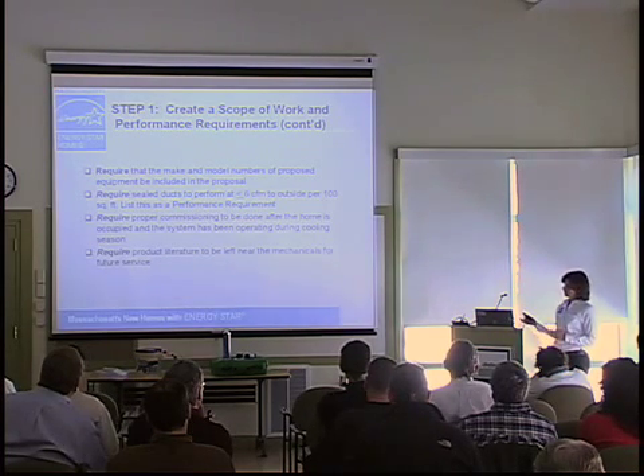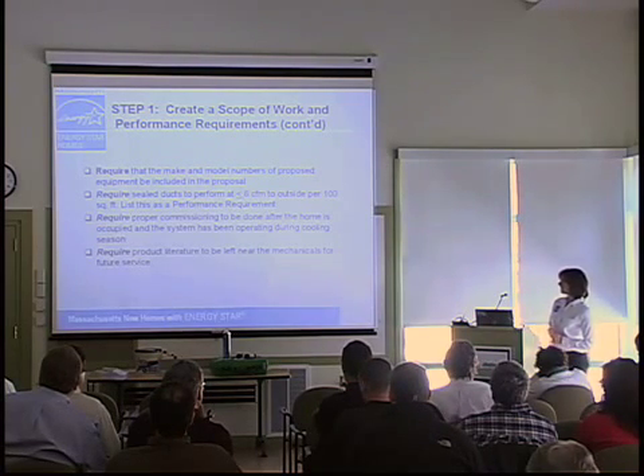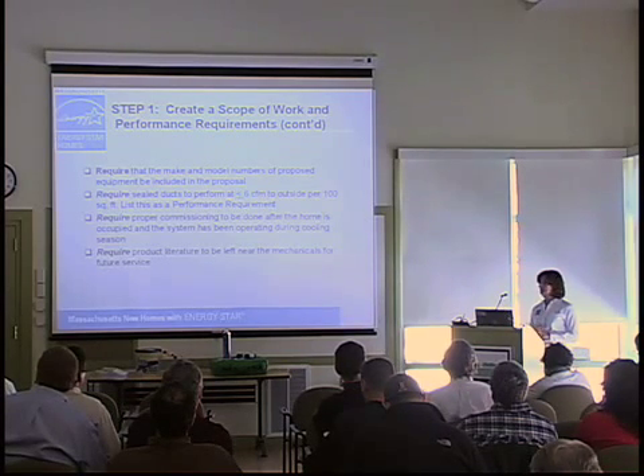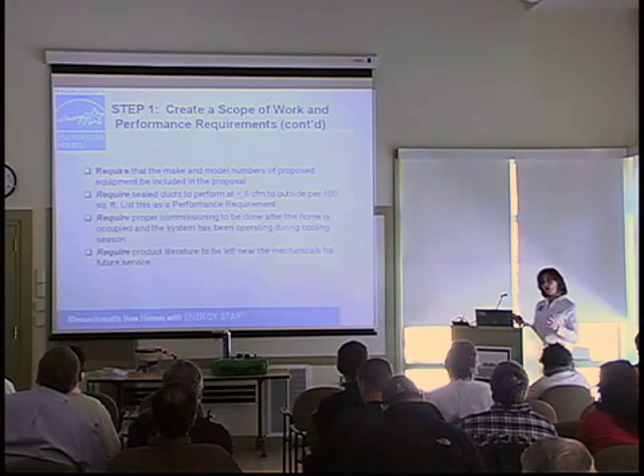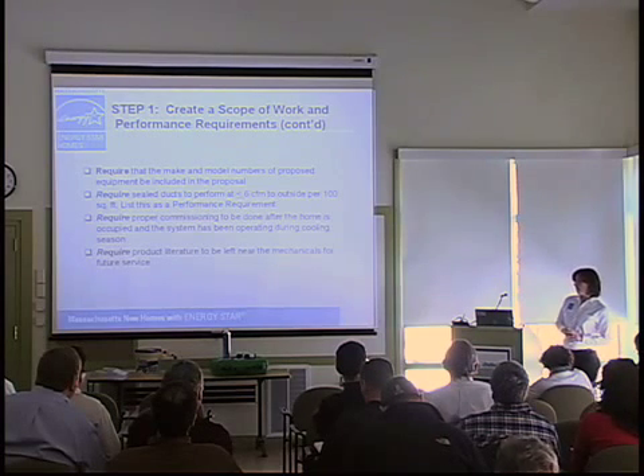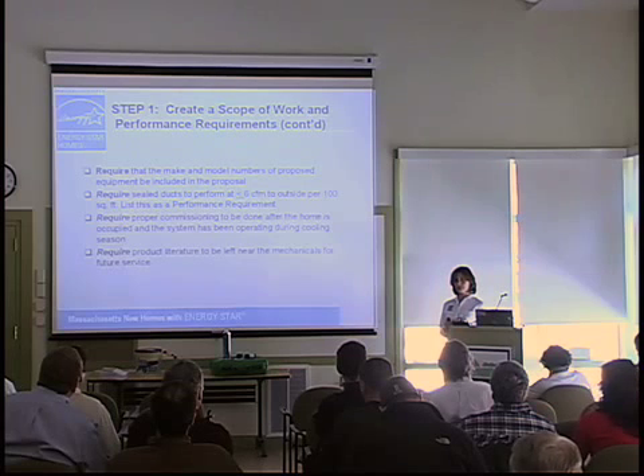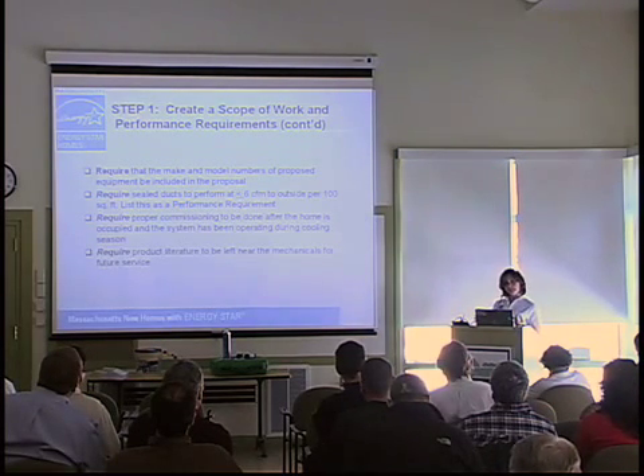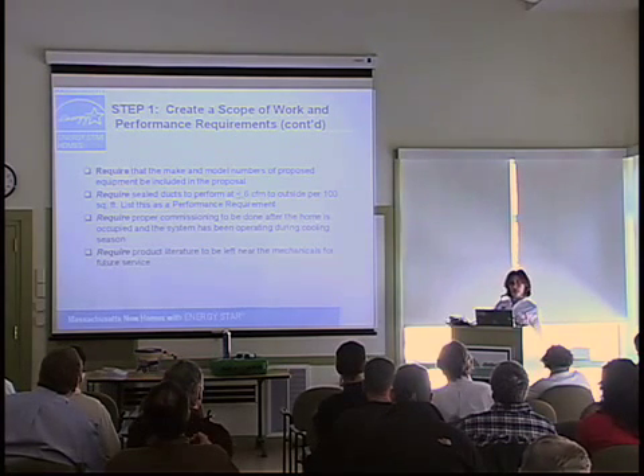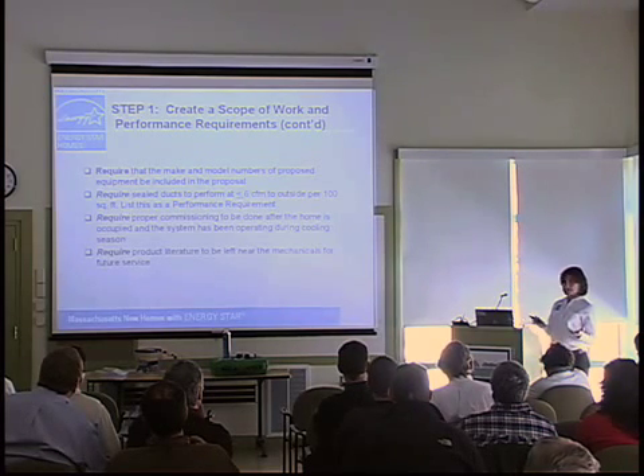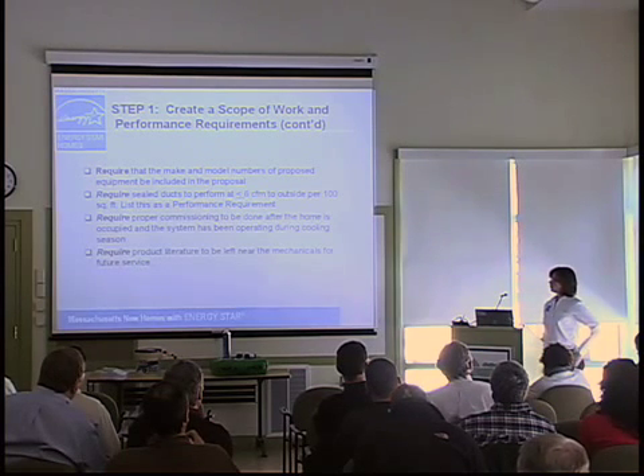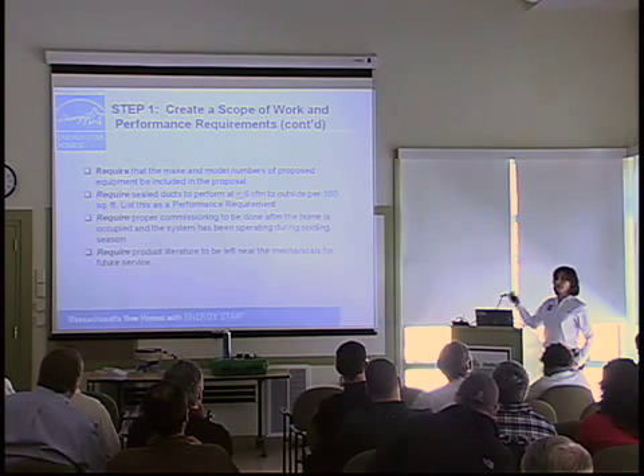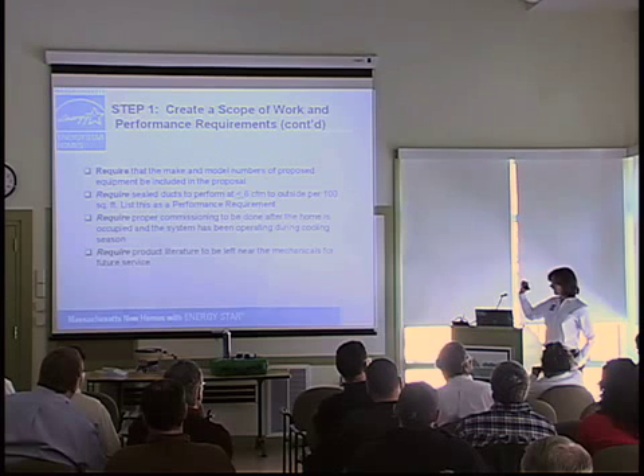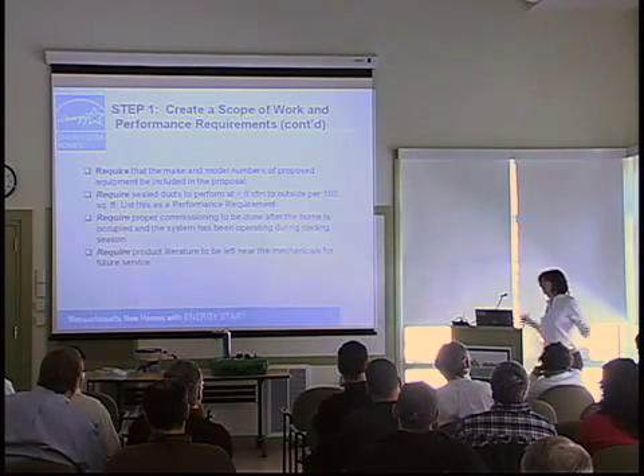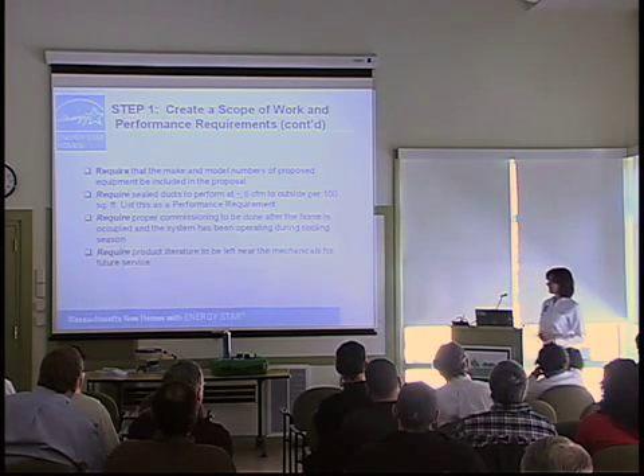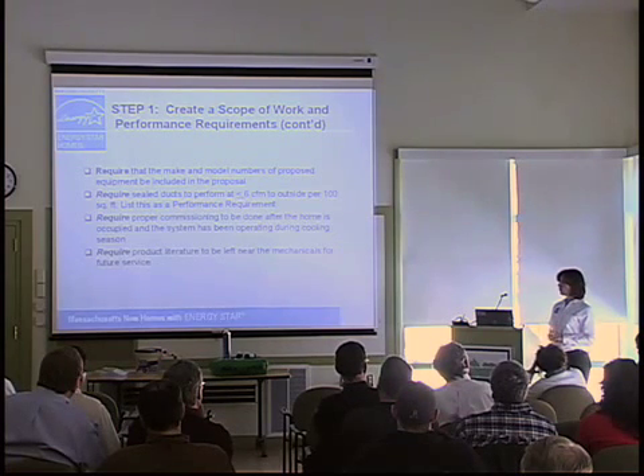Require proper commissioning. Another word for this: commissioning, startup, quality installation verification. This is to be done after the home is occupied and the system has been operating during cooling season. Not all installers do a proper startup, but it's definitely something that needs to be done. Condensers do not come out of the factory with a proper refrigerant charge. They're charged, but that needs to be adjusted based on how the airflow and the static pressures read throughout the duct system, as well as with the coil. So proper commissioning definitely adjusts your airflow. It tweaks out the system, and that'll change once the home is occupied and 10 people show up and they're living there, and maybe they bring a bunch of plants in the house, and the loads start to change, and that's why commissioning is a good thing to actually offer your new homeowner as an added-on service.